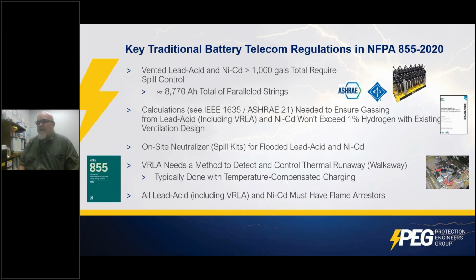I don't care if the manufacturer, even my own company, writes "sealed" on there; it has a one-way pressure valve, and they will gas a small amount. You have to do the calculations to show the AHJ that you're not going to exceed 1% hydrogen, or you've got to overventilate the space, and that's not a good thing from an energy perspective. You have to have on-site neutralizer spill kits for flooded lead acid and NiCad. And VRLA needs a method to detect and control thermal runaway.